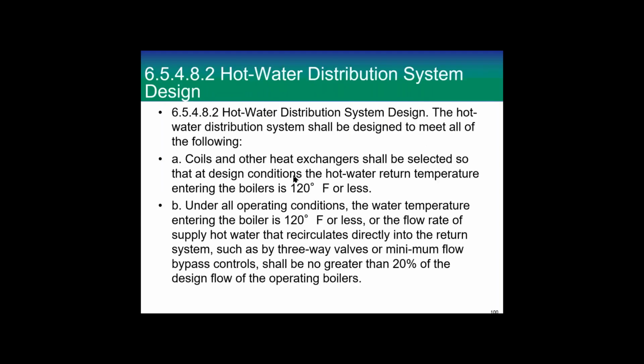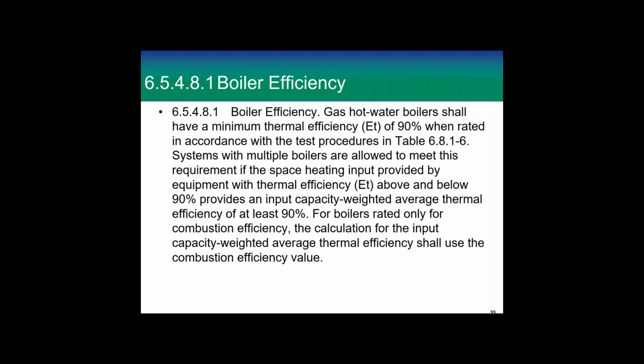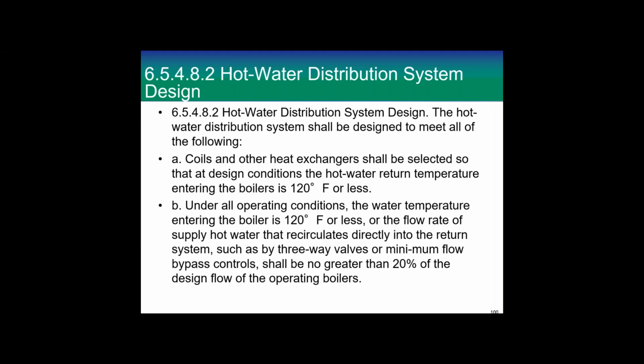There are some exceptions, but the boiler efficiency should be 90%. So that means you're going to use condensing boilers, and your hot water distribution system will return the water to the boiler at no hotter than 120 degrees. And if it operates so that the water temperature entering the boiler is 120 degrees or less, the flow rate of the supply water that recirculates directly to the return, by three-way valves, is no greater than 20% of the design flow to the operating boilers.